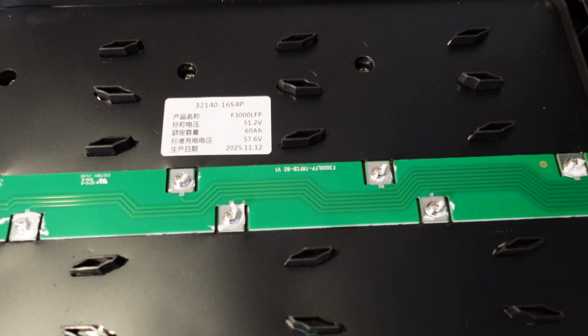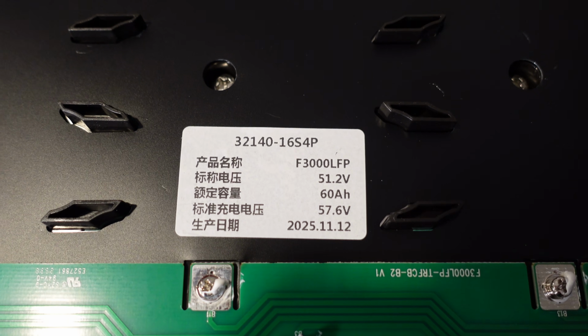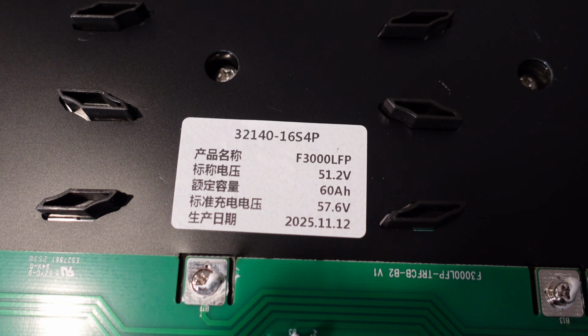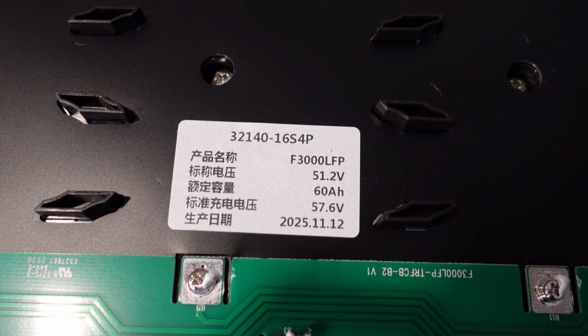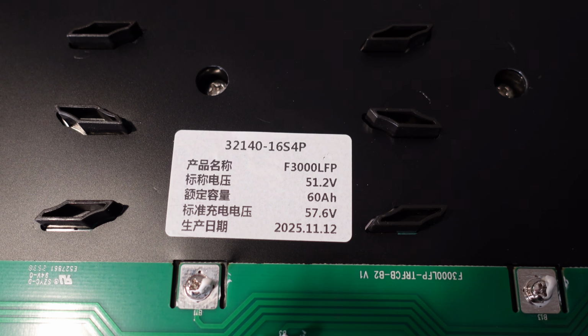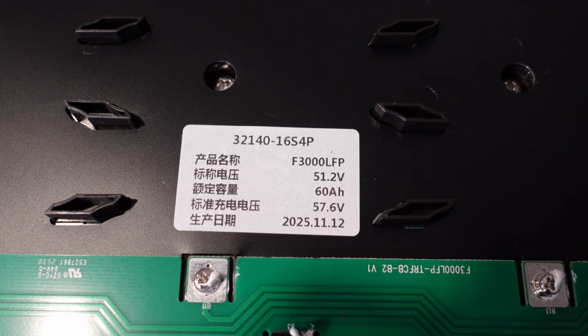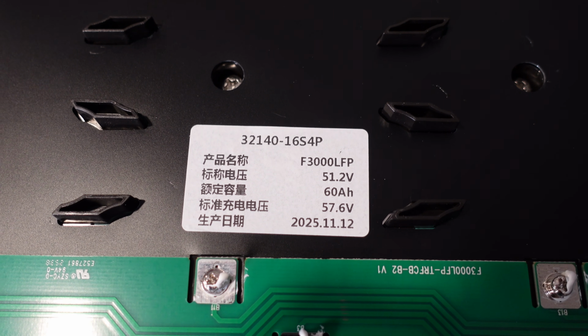Underneath the inverter, we have a little sticker describing our battery. Again, these are 32-140 cells, we already established that, 16S4P, so there are 4 cells wired in parallel, giving us our 60 amp hours. 16 in series gives us 51.2 volts nominal.